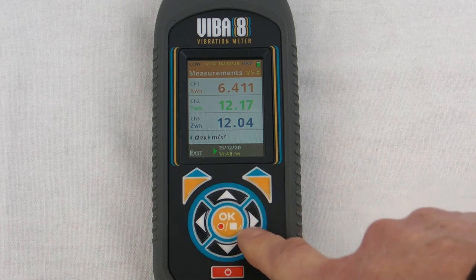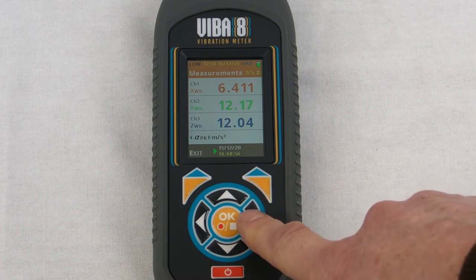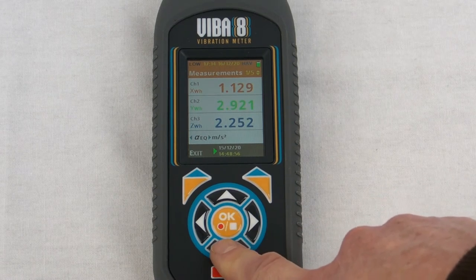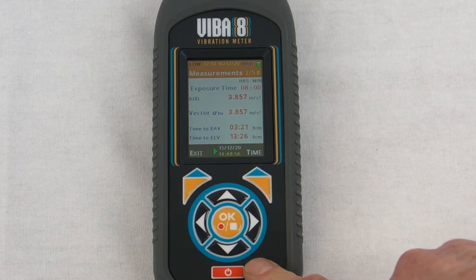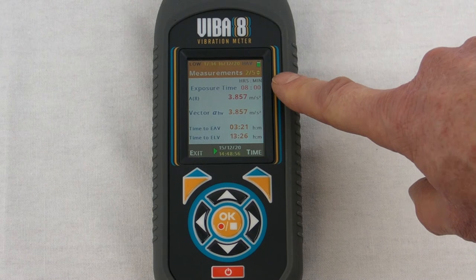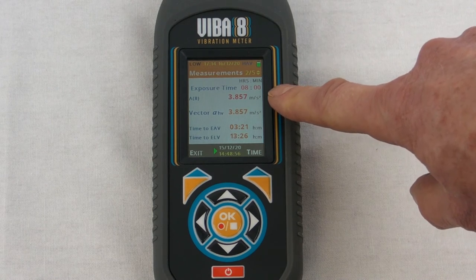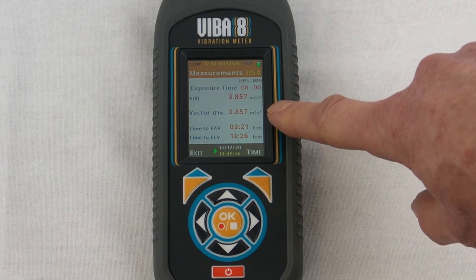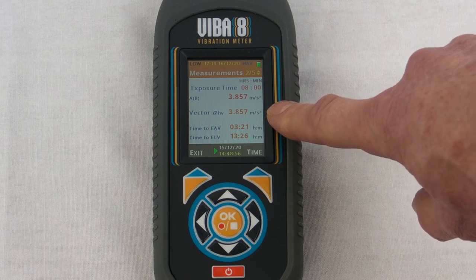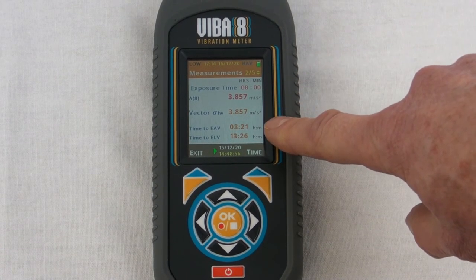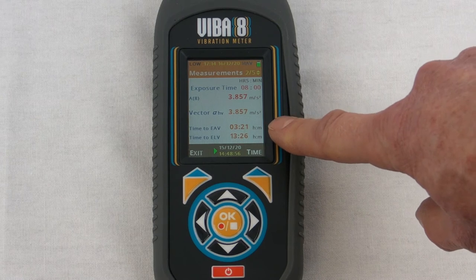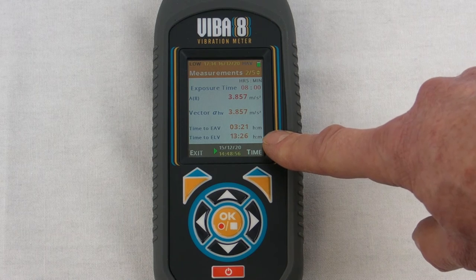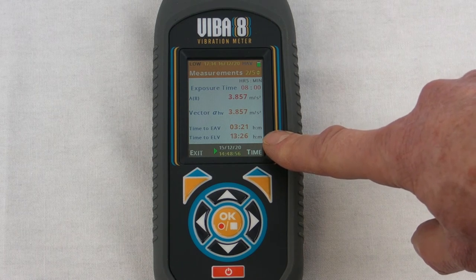So they're the three measurements we got for each of the x, y and z axes. You can also on the screen look at the peak value. Pressing the downward button key gives you another screen which shows all the exposure figures. So based on an eight hour working day that would give us the a8 exposure figure in meters per second squared, also the vector sum which of course is the same because we're basing it on eight hours. And then the time to reach the action value would be three hours and 21 minutes, alternatively time to reach the limit value would be 13 hours and 26 minutes.